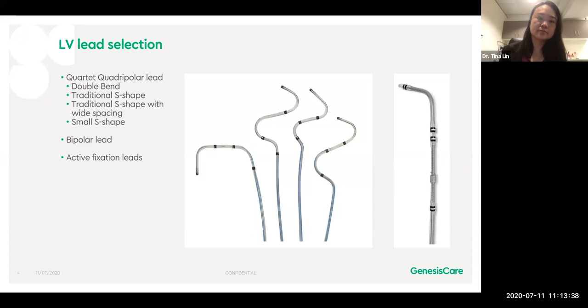So generally, to advance the LV lead, I generally start off with the stylet inside the lead. And once we get the lead beyond the sheath, I generally don't have the stylet all the way in, as this increases the stiffness of the lead and therefore increases the risk of dissection of the lead. However, there are different stylets that are available, including a combination stylet and guide wire stylet, which means that the tip is quite soft.